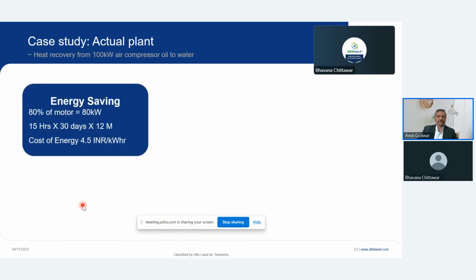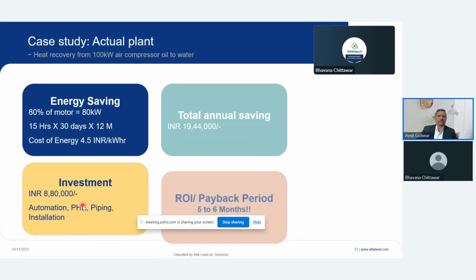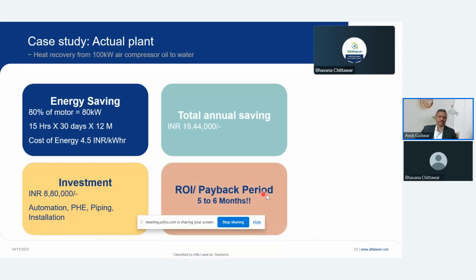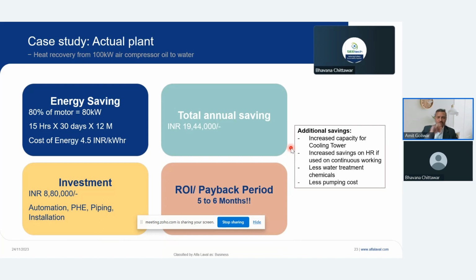This is the typical 100 kilowatt air compressor, which is very commonly available in any industry, any process plant, and there the actual payback has come to 5 to 6 months. This has been followed by one of a renowned MNC, and they have decided that they have 70 plus plants in India, and they are replacing all their compressors with this compressed air heat recovery, or hot water generation from compressed air oil.